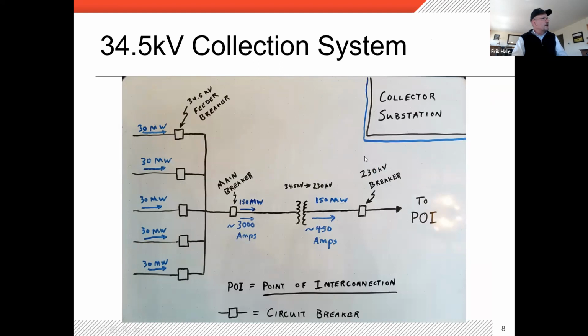What I was showing on the previous slide is just this one point, coming into what I'm depicting here as the collector substation. I have slides coming up showing examples of these from Google Earth. This square here is a medium voltage circuit breaker, which I'll also show on the Google Earth images. In this case, we've brought together 5 of these, running them into bus work in the substation, so now you're up to 150 megawatts in this example. You'd then run them through a transformer to transform it to high voltage—230 kV in this example, a common transmission voltage in the West. From there, it leaves the substation and goes to the point of interconnection.